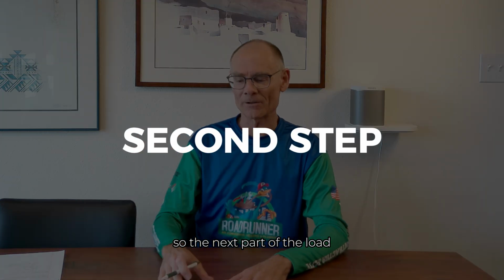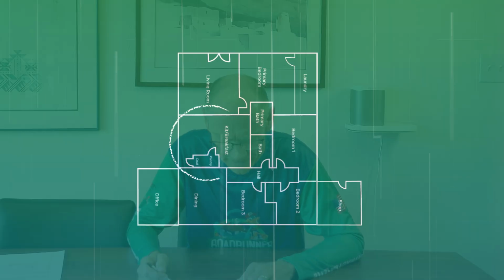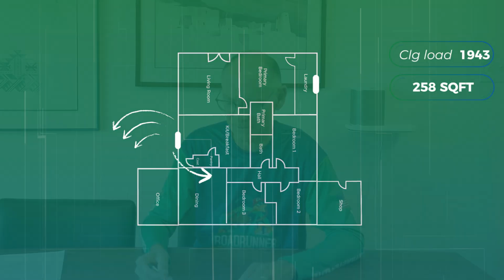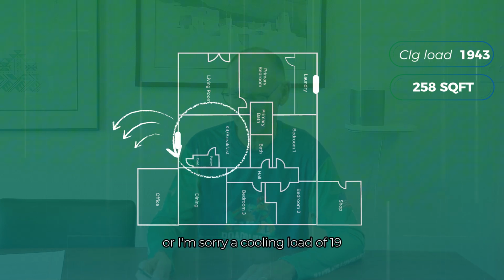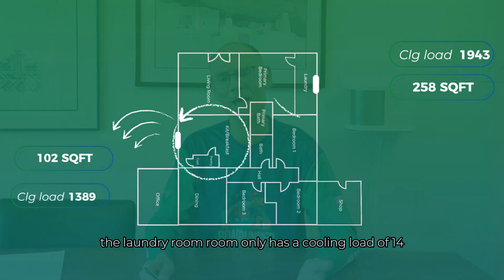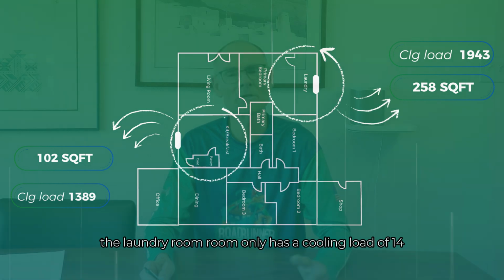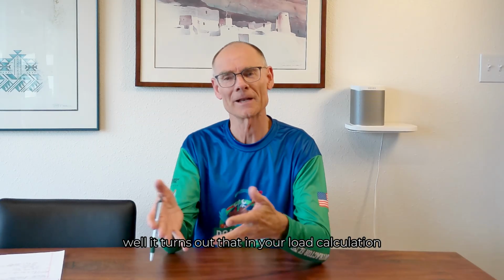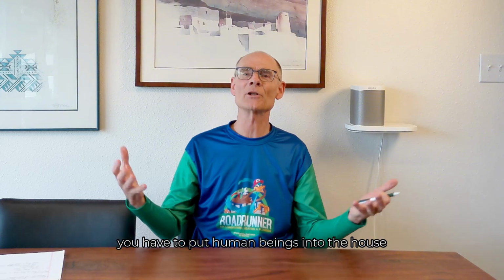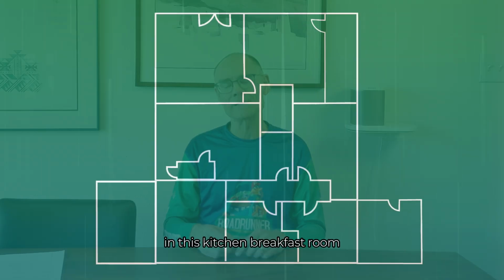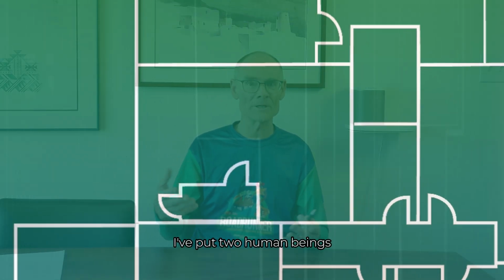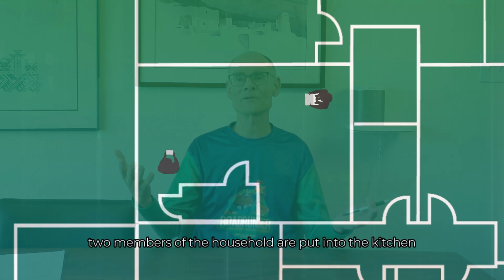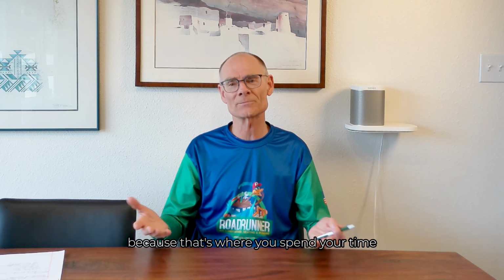The next part of the load calculation is the cooling load. The kitchen has a cooling load of 1,900, while the laundry room only has a cooling load of 1,400. Well, it turns out that in your load calculation, you have to put human beings into the house. In this kitchen breakfast room, I've put 2 human beings. 2 members of the household are put into the kitchen because that's where you spend your time.